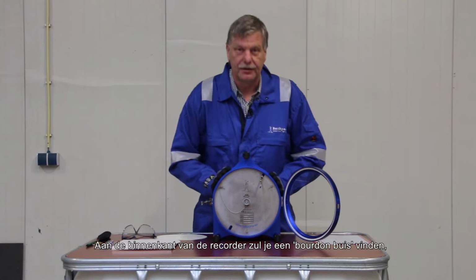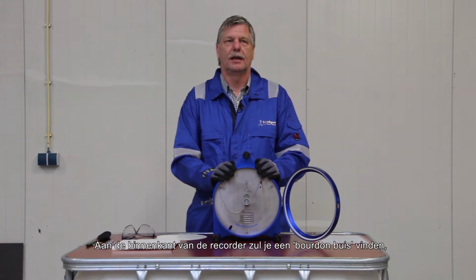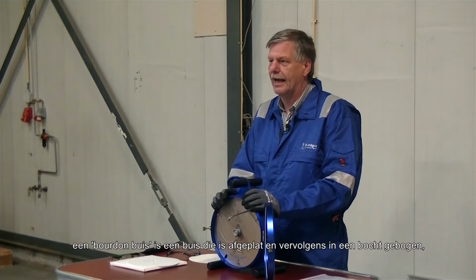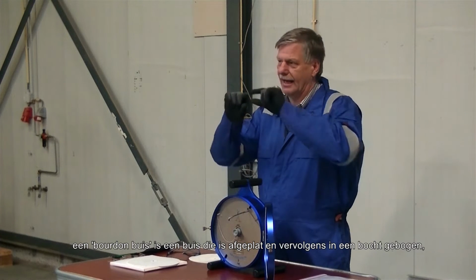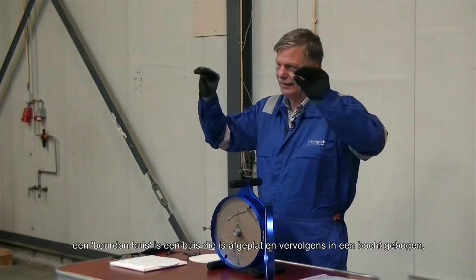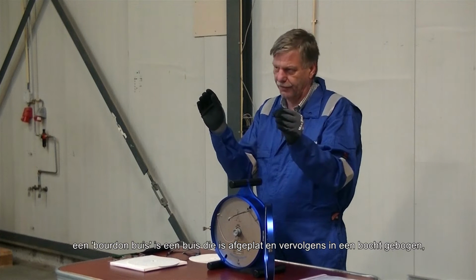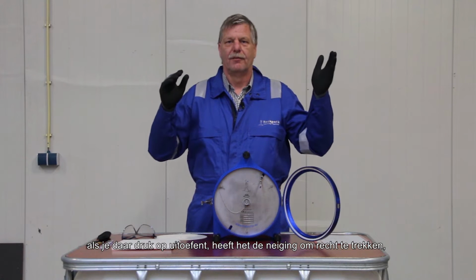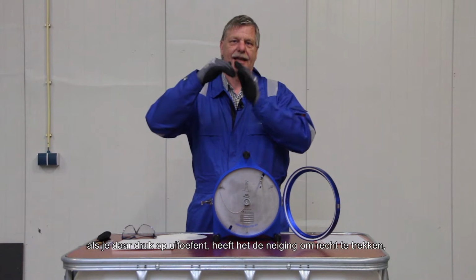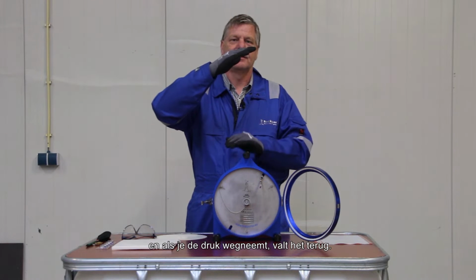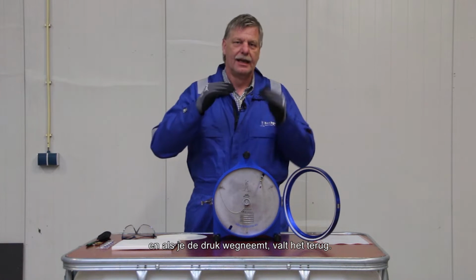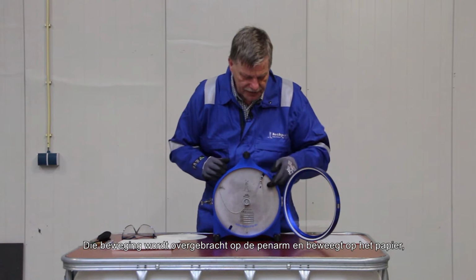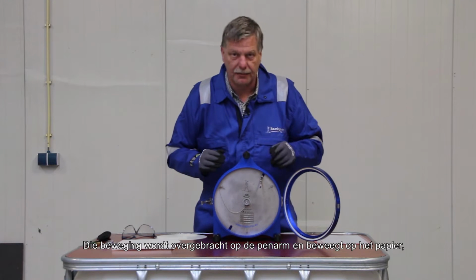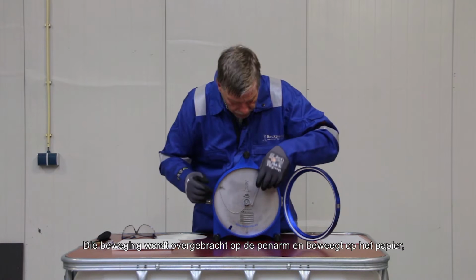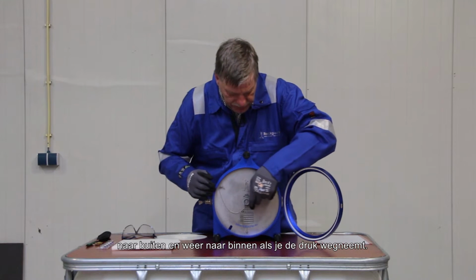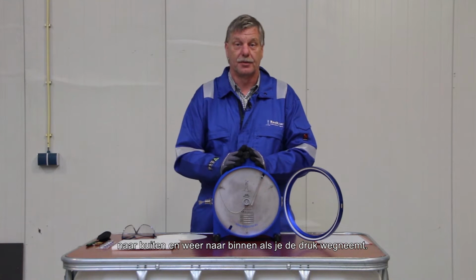On the inside of the recorder you'll find what they call a bourdon tube. It's a tube that's flattened, then bent in a curve, and when you put pressure on it, it has the tendency to straighten out, and when you take the pressure off, it falls back. That motion is transferred onto the pen arm, which moves outwards on the paper and back inwards when you let go of the pressure.